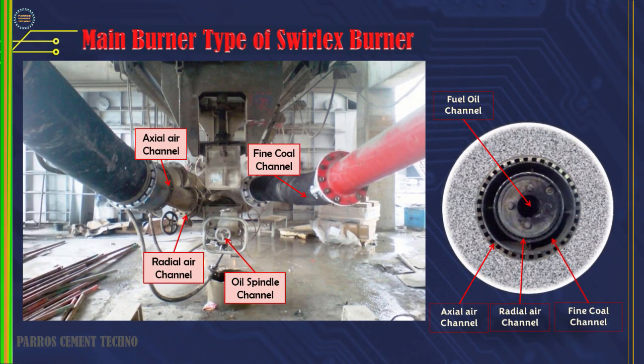This is the kiln main burner type, the Swirlex burner. This type of burner cannot change the primary air pressure because the axial nozzle gap is fixed, and can only go forward or backward between 0 to 15 mm, which does not affect the air pressure. For the operation of this burner, adjust the axial air valve opening 65 to 70% and radial or swirl air 30 to 35%.